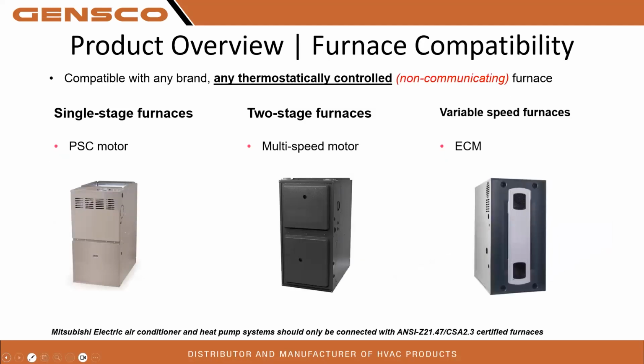Furnace compatibility. These coils are compatible with anything that's thermostatically controlled and non-communicating, meaning anything 24-volt controlled. If you have 24-volt, your standard red, common, white, yellow terminals, this coil can be used with that. Anything that is DC controlled or communicating back and forth will not work with that. It has to be 24-volt controlled unless that furnace has the ability to be changed over to 24-volt controls for communication. Otherwise, you're going to be stuck with the 24-volt.